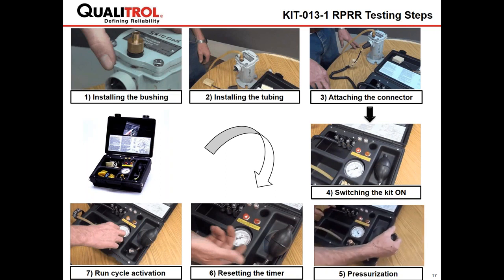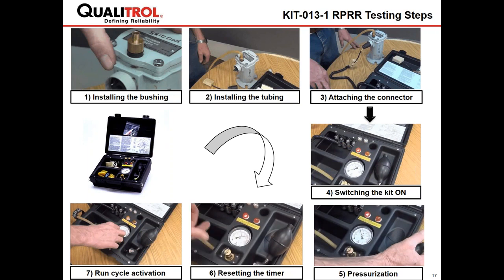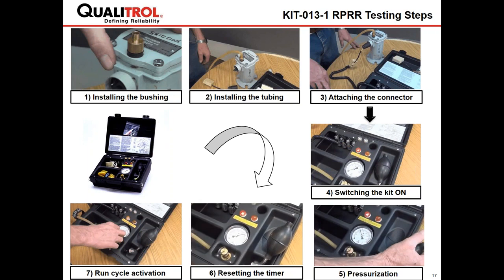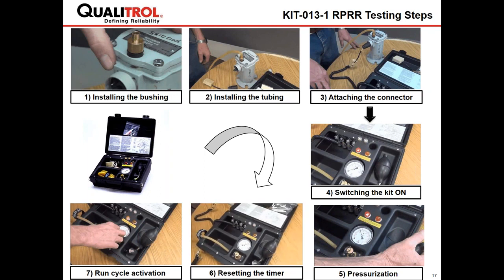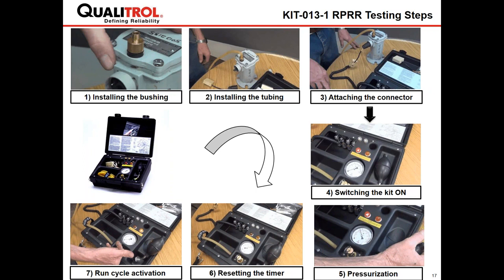Then you will pump the unit up to the pressure required on your unit. The table in the instructions on the lid of the case lists the various pressures that you need to specify for your unit. You reset the timer, and then finally you pull the pop-off pressure valve, which will portray the sudden change of pressure and activate your unit. Therefore, the light will turn on and say, yes, the unit did trip when there was a rapid change of pressure. A full video will be available at the end of the webinar, but it is also on our YouTube channel under Qualitrol.